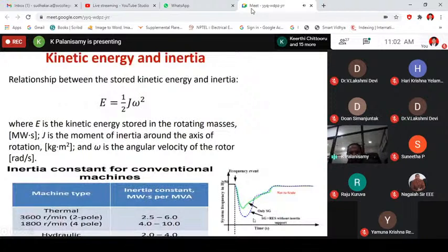So this is what I was talking about. When we have only conventional synchronous generators and a fault occurs, the kinetic energy stored in the rotor, a big rotating mass of the synchronous generators, will support by being released from the flywheel or the rotor, so that the rate of change of frequency is somewhat less. But now, most of the time the rotating part, even for the windmill, is decoupled. It means that between the wind generator and the grid, your power converter is sitting.